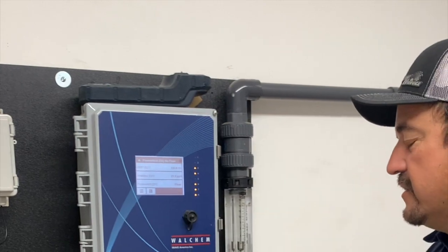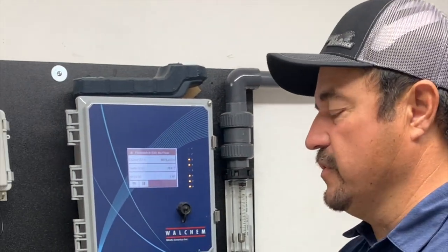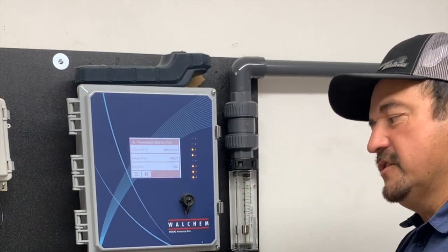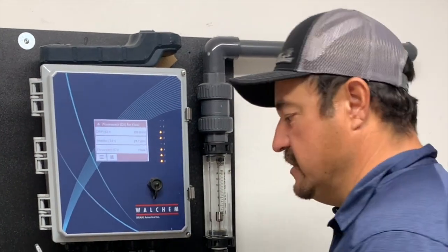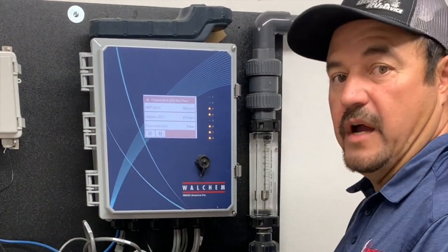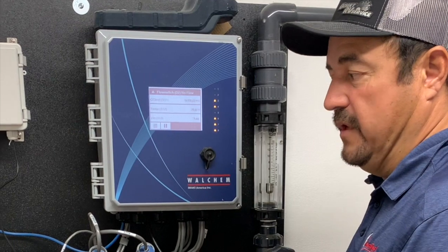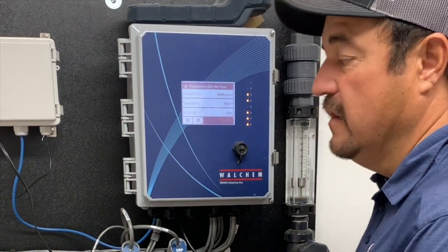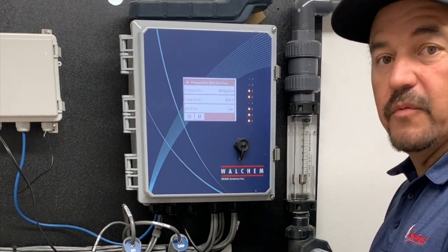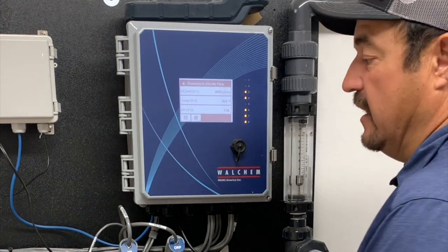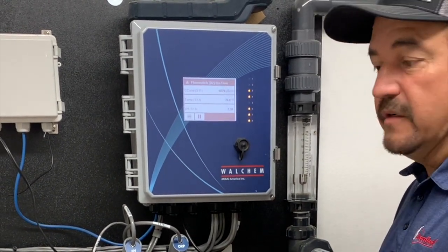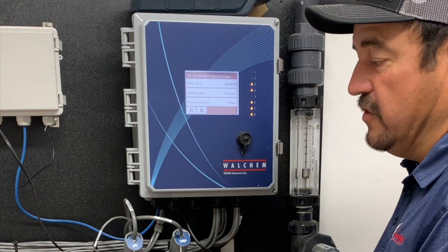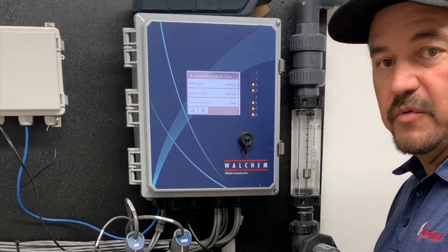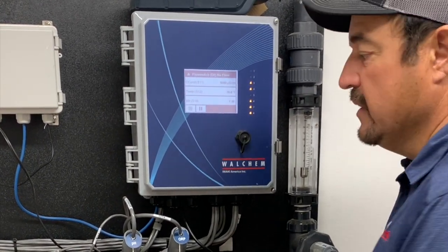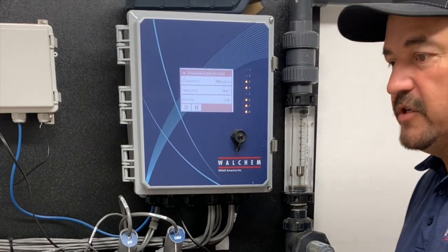Now I've always been asked, how often should we calibrate our probes? It's always going to vary. Some processes are very clean and you really won't have to calibrate them more than maybe once a week, even once a month. I would recommend that you do calibrations at least once a month, at least a process calibration. If possible, at least you could use a buffer to do your calibrations at least once a month would be ideal, but at least do a process calibration.